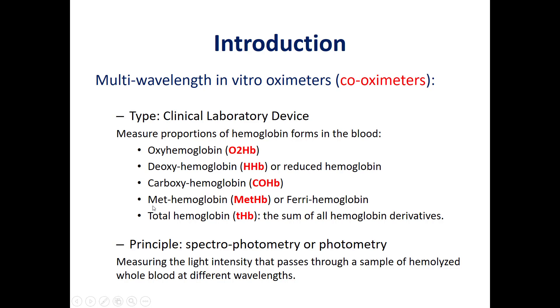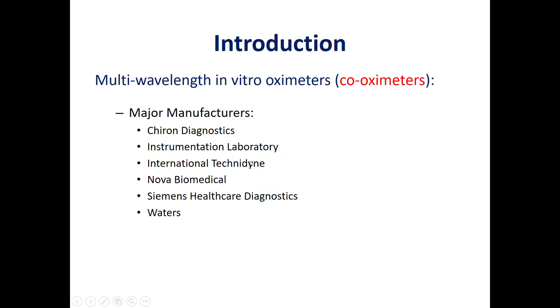After measuring these four types of hemoglobin, we can calculate the total hemoglobin. The principle of this lab co-oximeter involves a hemolyzed whole blood sample. We pass light through it and measure absorbance at different wavelengths to measure the different hemoglobin derivatives. Here we can see some major manufacturers of lab co-oximeters.